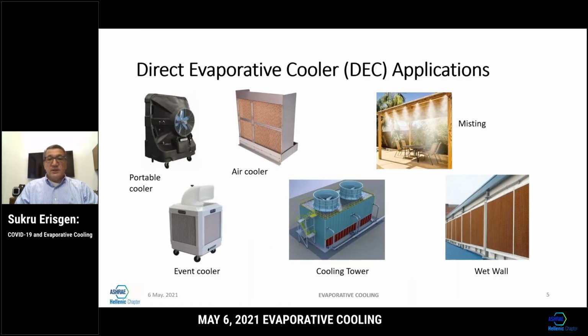When we look around, we see many ways these direct and indirect versions can be used. In the United States, direct evaporative coolings are very popular as portable coolers and event coolers. Portable coolers have one fan and evaporative media on the other side; it is one directional. Event coolers pull air from all four sides, and the fan blows it from the top into an event. It can be ducted or just freely blowing into the space. All you need is water and electricity.